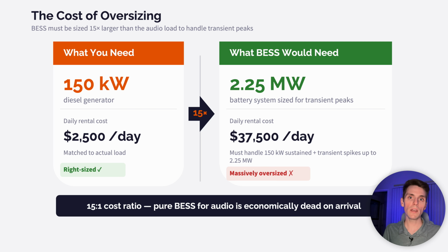A festival needing 150 kilowatts of audio power would require 2.25 megawatts of battery and inverter capacity to handle those transient spikes. That's $2,500 a day for diesel versus $37,500 for BESS. It's a 15 to 1 cost ratio. So pure BESS for audio is economically dead on arrival.